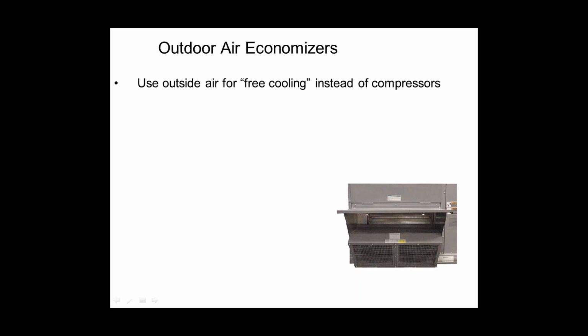So if you didn't know, an outdoor air economizer is used for free cooling. At a residential house, if you want to get air conditioning in Chicago or Illinois in the middle of the winter, you probably don't turn your air conditioner on. You probably just open a window, right? Well, the problem with most commercial buildings is they don't have windows that can be opened. And even if they do, people don't open them at the right time, right? Operable windows is very challenging to get people to do what they're supposed to do.